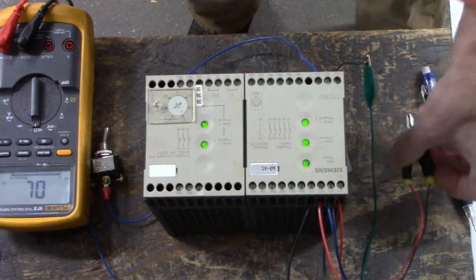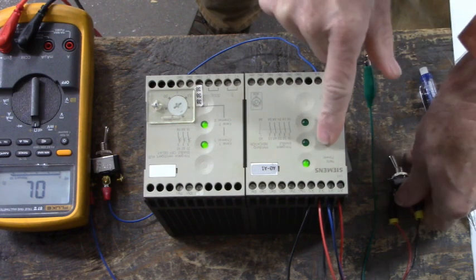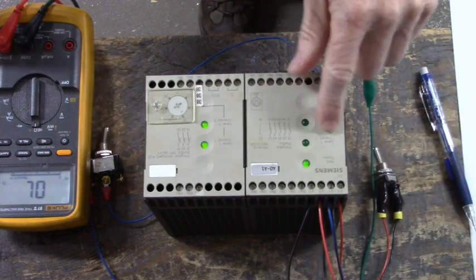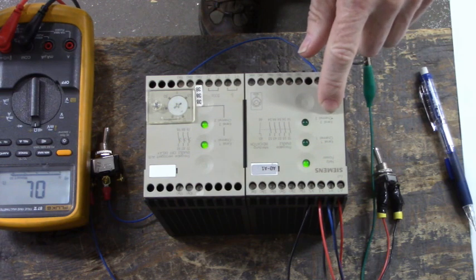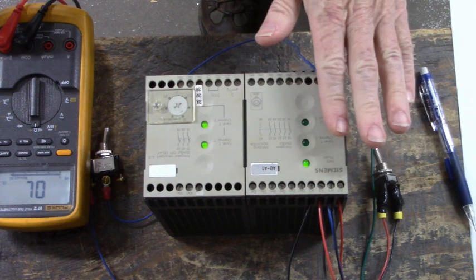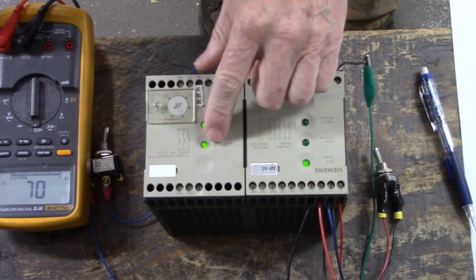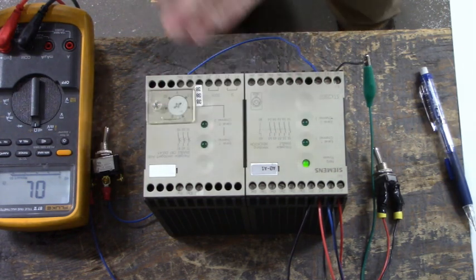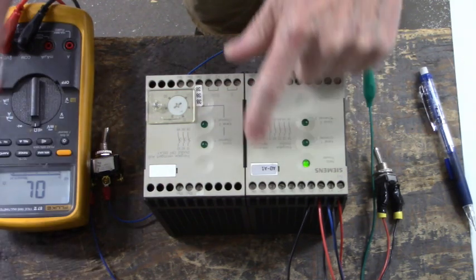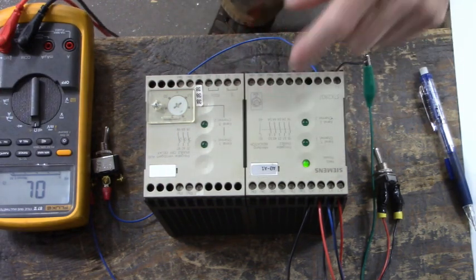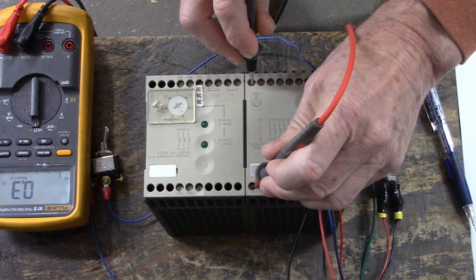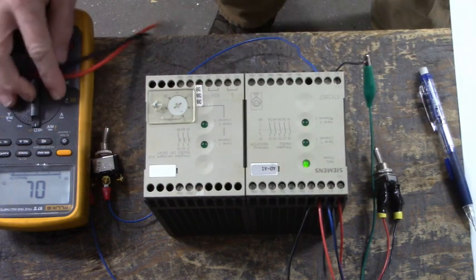Alright. Now, we're going to open this switch. These two LEDs just turned off. And the channel 1 and channel 2 contactors, they've opened up. And here, after almost 12 seconds, this side turned off. Now, let's go check 65 to 66. That's normally closed. Yeah, that's good.